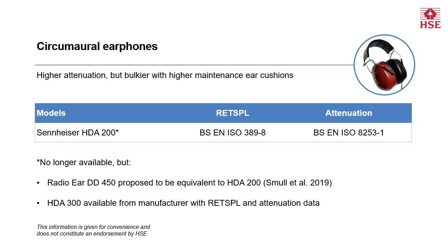For circumaural earphones, there is only one model with RETSPLs and attenuation data in the standards, and that is the HDA 200. Unfortunately, this is no longer available. It was replaced by the HDA 300. The RETSPLs and attenuation data are available from the manufacturer, but the attenuation is not as good as for the HDA 200. However, there is another model called the RadioEar DD450, which has been proposed to be equivalent to the HDA 200. Other makes and models of circumaural earphones are available.